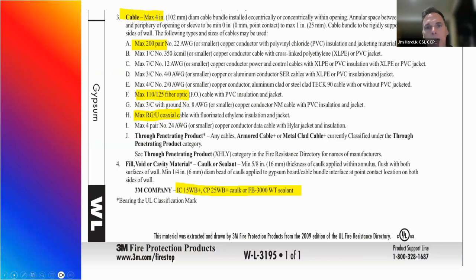You're probably wondering, why do we have multiple products that will address the same condition? Each of these Firestop sealants have their own unique properties. The 3000 WT sealant, for example, is silicone-based. So if you have a situation where you're requiring a watertight seal, that might be the product that you want to look at using. Whereas the IC15WB is a more cost-effective sealant to use, but it's not necessarily good for wet environments. So that's why we give you some options when you're trying to determine what products to use. Next slide, please.